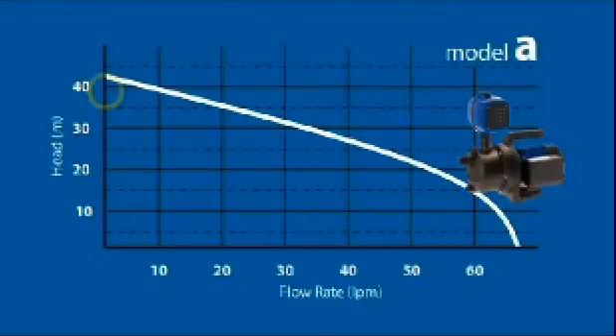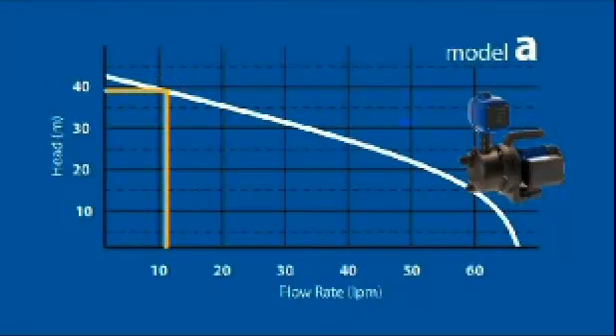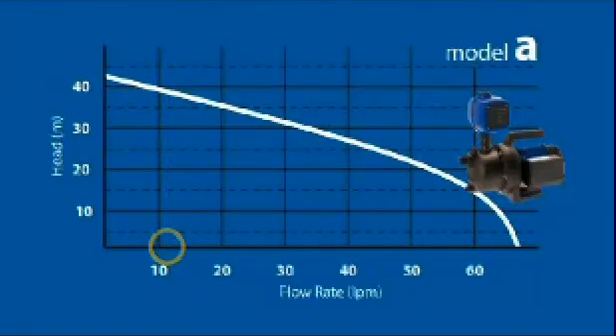On the graph, find 39 metres of head on the vertical axis and run an imaginary line across the graph. At the point your line crosses the pump curve, draw another line directly down the graph to the flow rates along the horizontal axis. This is the flow rate your pump can deliver when working against the pressure you have calculated. Is the pump able to produce the flow rate required? In the case of model A, the answer is no.